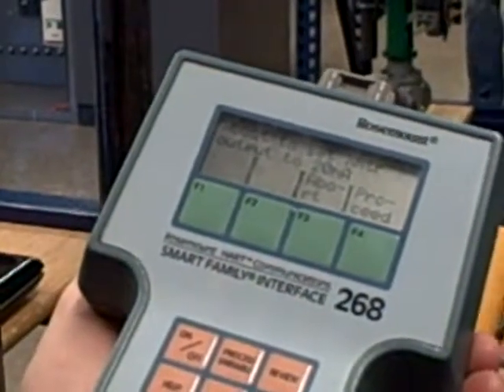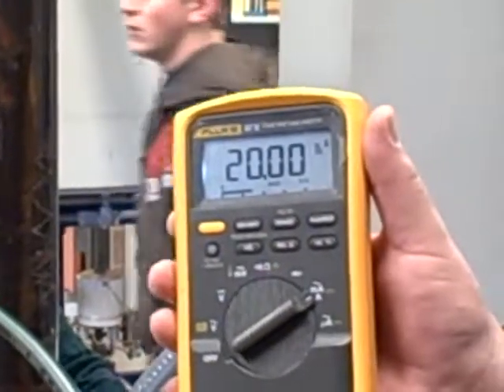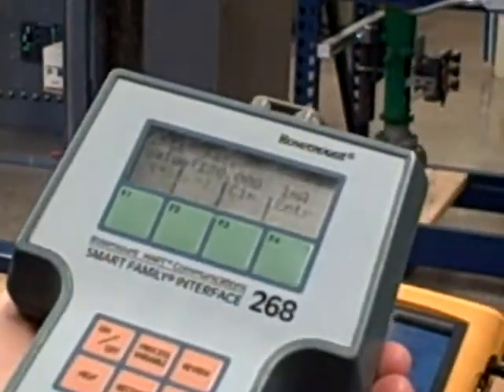About to set transmitter output to 20 milliamps. I'm going to hit the proceed button. And once again, it will ignore whatever pressure is coming in. It will just force the output to 20 milliamps. And we verify at the meter, indeed, it is at 20 milliamps.